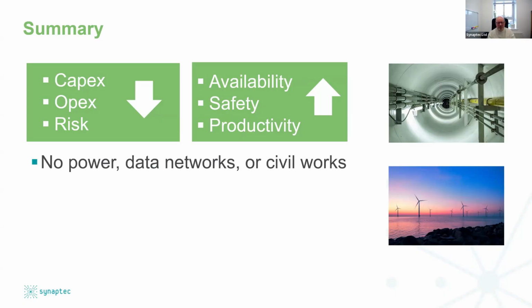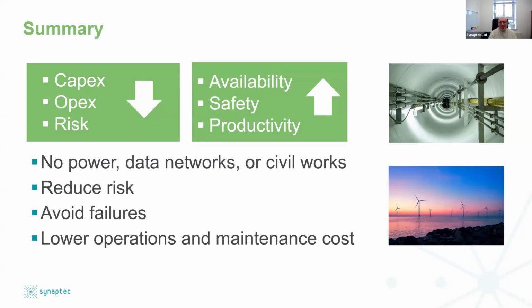And again, just to re-emphasize, the whole point of this technology that we really want you to understand is it really does work with no power, no data networks, and no civil works. It does fundamentally mitigate risk because we're giving you advanced warnings so you've got time to avoid the cable going bang. And it's about avoiding those failures and those prolonged outage costs and repair campaign costs, which can be horrific. But day to day, even if that never happens, the system will help you to optimize scheduled maintenance cost and reduce that regular maintenance cost regime because we're able to identify what needs focus and attention rather than having to check everything.